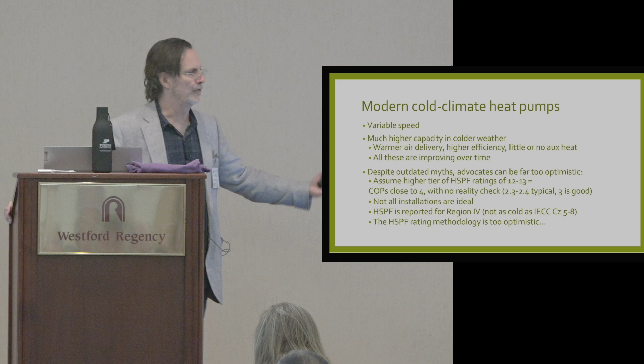So you have this weird, unintuitive thing where you can say, I have a great cold climate heat pump, but if I were to look at the HSPF rating in climate region 5, it would be lower than the heating efficiency HSPF rating in climate region 4. It's always lower in the colder climate than in a milder climate because it's colder.